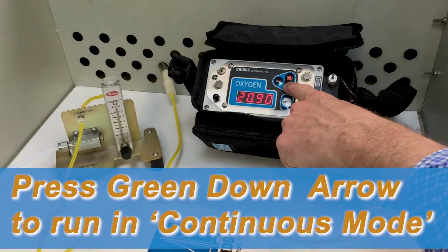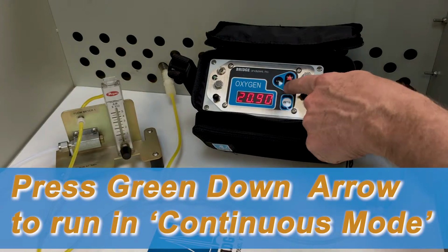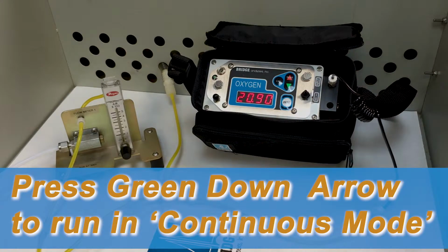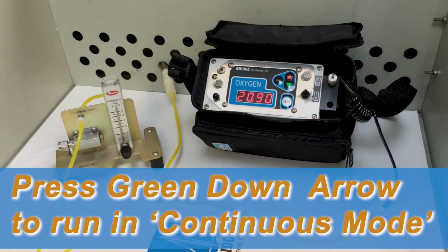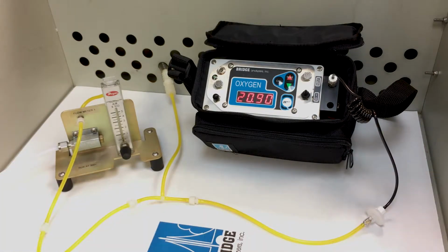You have to press the zero or press the green down arrow to get it into continuous mode, and that is needed if you're in the discrete test and hold mode. When you first turn it on and zero, it will be in a continuous mode, so you can just leave it in that mode if you like.